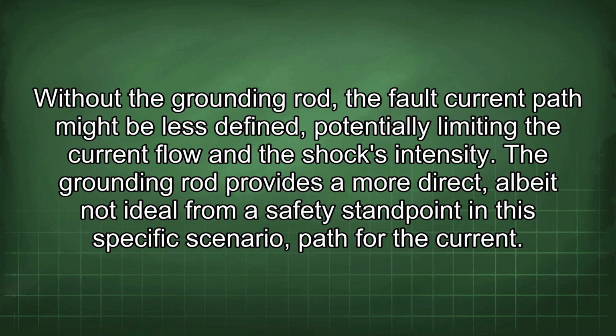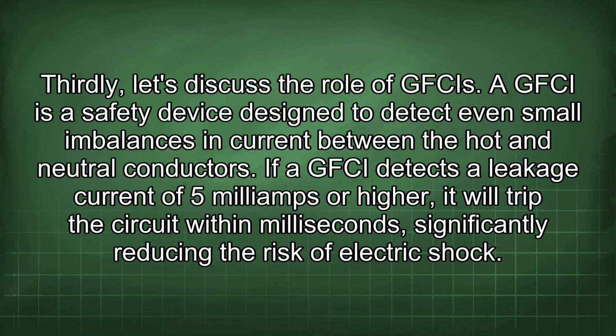Without the grounding rod, the fault current path might be less defined, potentially limiting the current flow and the shock's intensity. The grounding rod provides a more direct, albeit not ideal from a safety standpoint in this specific scenario, path for the current. Thirdly, let's discuss the role of GFCIs.